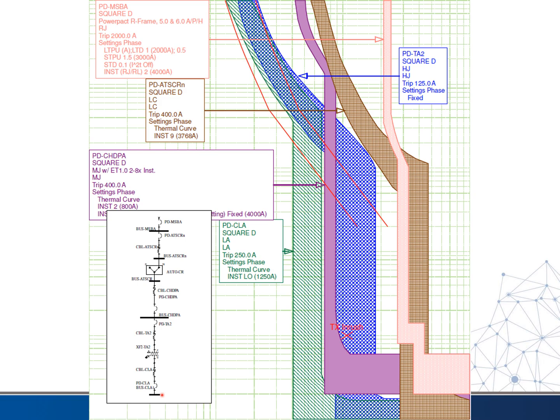You can have multiple branches throughout your system, which makes these studies time-consuming because you have to keep picking all these different pathways. Anywhere there's a breaker, the curve for that breaker is shown — for instance, PDMSBA is the pink one, PDCHDPA is the purple one, and PDCLA is the green one. The idea is that as we come down through the system, the curves would come down in order. So PDCLA, being the closest to the load, is the furthest to the left. But moving to the right, we can see a couple of problems.